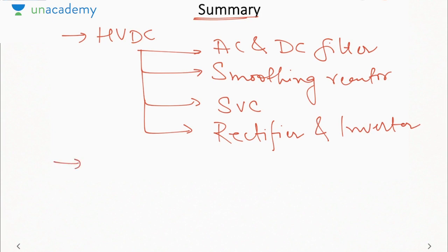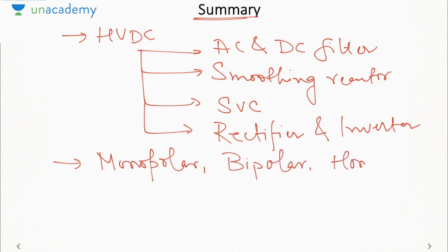Then we saw type of link, that is monopolar, which used only one polarity or one conductor. Then bipolar, which used two conductors having opposite polarity, and homopolar, two conductors having same polarity. And then we saw advantages and disadvantages of HVDC.